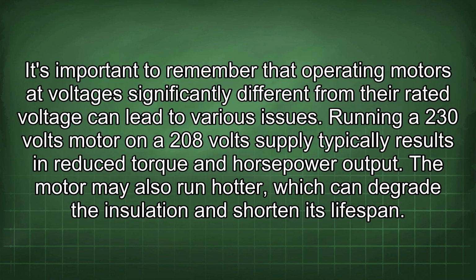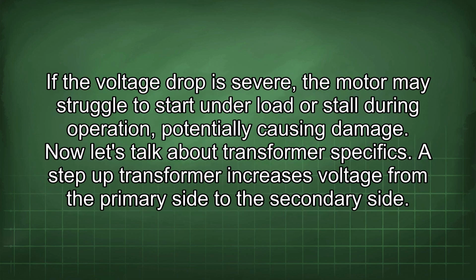It's important to remember that operating motors at voltages significantly different from the rated voltage can lead to various issues. Running a 230 volts motor on a 208 volt supply typically results in reduced torque and horsepower output. The motor may also run hotter, which can degrade the insulation and shorten its lifespan. If the voltage drop is severe, the motor may struggle to start under load or stall during operation, potentially causing damage.